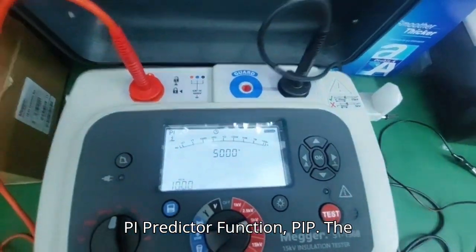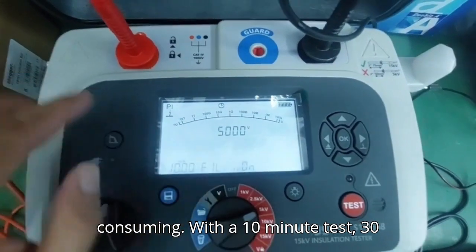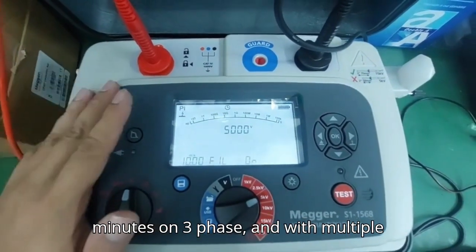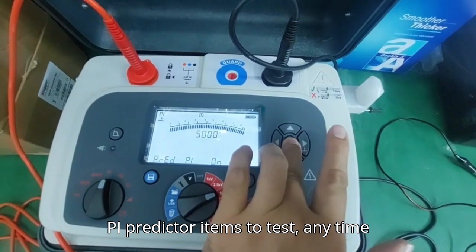PI predictor function (PIP). The polarization index test can be time-consuming with a 10-minute test, 30 minutes on three-phase, and with multiple items to test, any time saved is a bonus. PIP does just that.